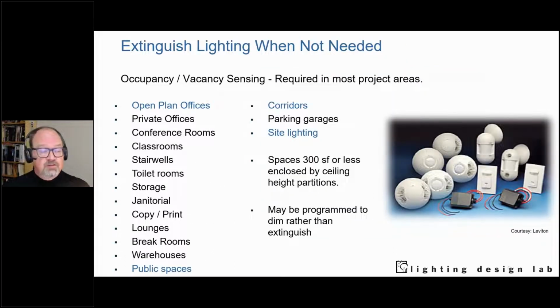But most of these codes come down to one basic element: turn the lights off when we don't need them to be on. Occupancy or vacancy sensors are now required in most project areas—offices, break rooms, conference rooms, classrooms, corridors, stairwells. The number of places that you don't need an occupancy or vacancy sensor is lower than the number of places that you do on most projects now.